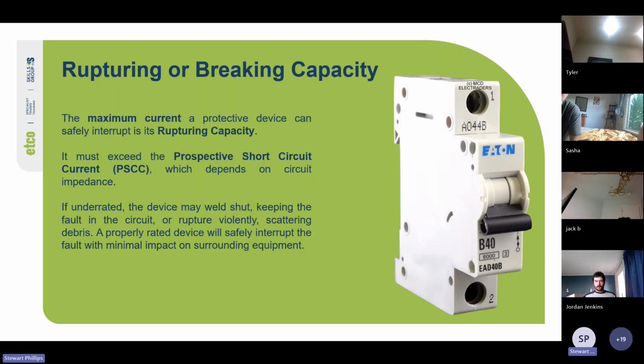Cool. Then you've got your rupturing or breaking capacity. It's the maximum current a protective device can safely interrupt. It must exceed the prospective short circuit current, or PSCC, which depends on circuit impedance. If underrated, the device may weld shut, keeping the fault in the circuit, or rupture violently, scattering debris. A properly rated device will safely interrupt the fault with minimal impact on surrounding equipment. So if you have a 6 kA breaker and it experiences a 10 kA prospective short circuit fault, if it welds itself shut, that current flow will continue, causing fire or electric shock, or it will explode, which could take out other parts of the board as well, causing fire inside the switchboard.